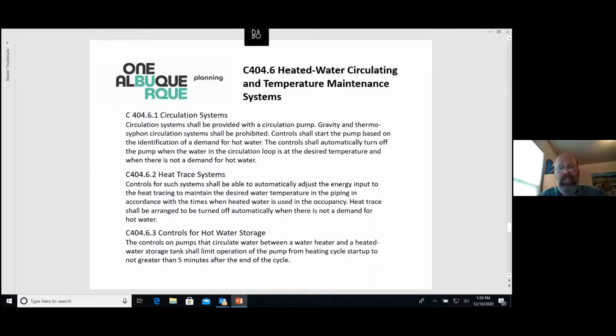Heat trace is a way of keeping the piping hot. Again, it's going to operate the same way, where it'll have a sensor in it, and when the water reaches a temperature, it turns it off. When it cools down, it turns it on. It doesn't so much circulate as it does just maintain the heat throughout the whole system. They have a 5-minute limit at the end of the cycle for the pumps to operate. So if you're circulating hot water through the building, at the end of 5 minutes, it shuts off once it's no longer needed.